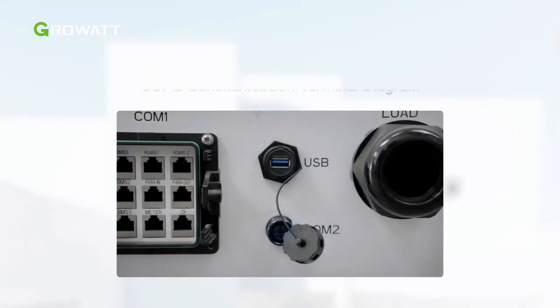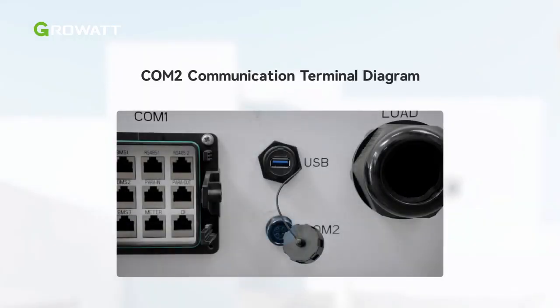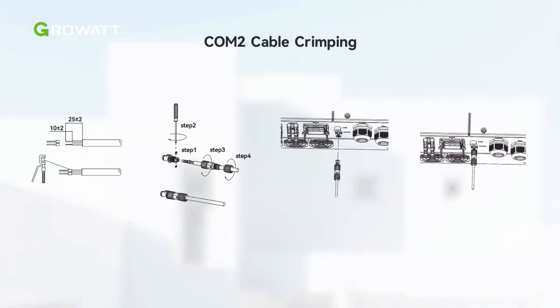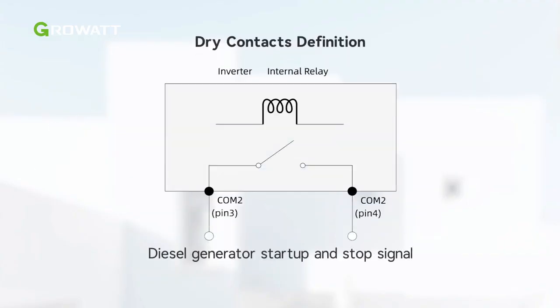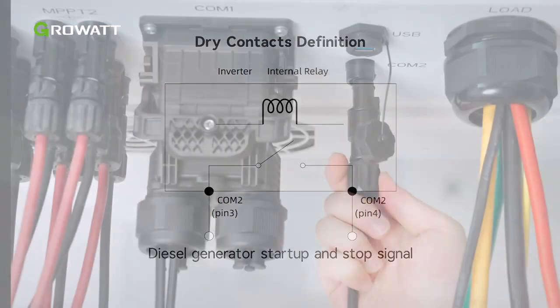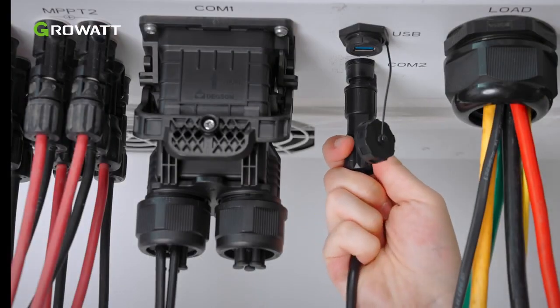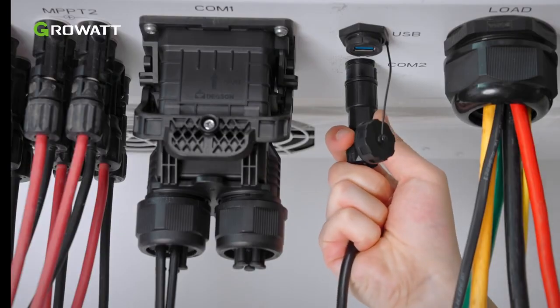The position of COM2 terminal is as illustrated. The COM2 terminal is used for generator startup, generator stop, and emergency stop. Crimp the COM2 cable as the figure shows. The COM2 communication terminal contains 2 dry contacts, voltage-free. Pin 1 and 2 are for emergency stop signal. Pin 3 and 4 are for generator startup and stop signal. Connect the COM2 cable to the COM2 terminal on the inverter.